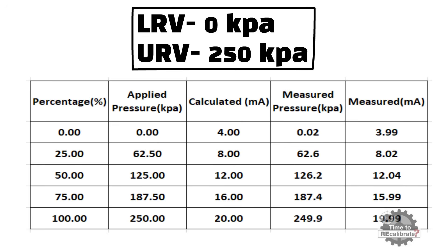Now repeat the same steps for 50% of input, 75% of input, and 100% of input. For example, apply approximately 125 kPa pressure to the transmitter and note down the measured pressure value from the transmitter display. The measured pressure value should be nearest to 125 kPa. At the same time, note down the value of milliampere from the digital voltmeter. The measured milliampere value should be nearest to 12 milliampere.